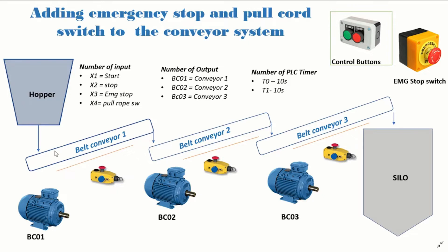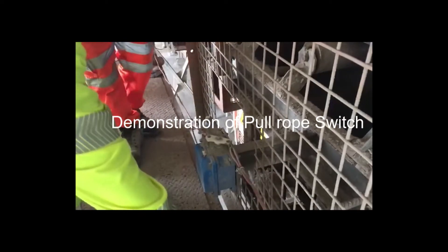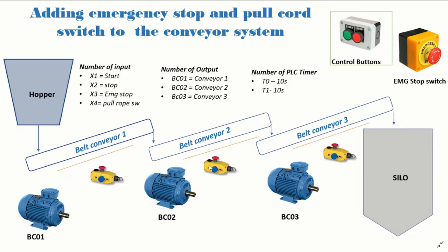Let's say for instance, whilst a technician is walking along, the conveyor is trapping them. The technician, operators, or workers should be able to stop the conveyors wherever they are to prevent injury. To do this, we have what we term the pull rope switch — we can see it in yellow right here. There is a rope connected from this hook of the pull rope switch to the other section of the conveyor so that it can be pulled whenever you want to stop it. We have three of them connected to all three parts of the conveyor; they will all be in series and given one input.